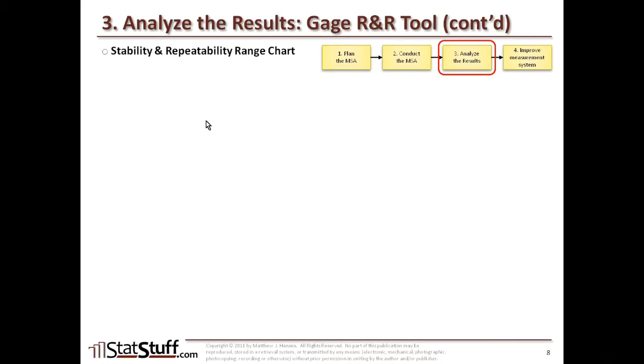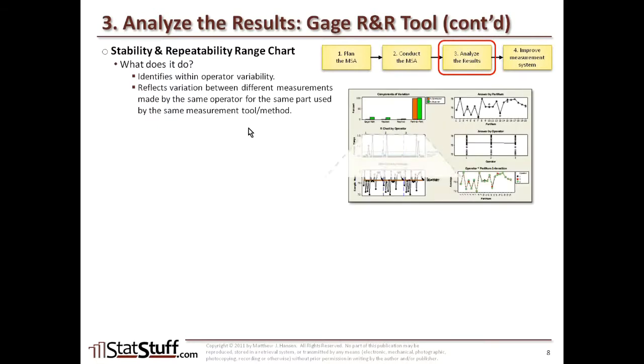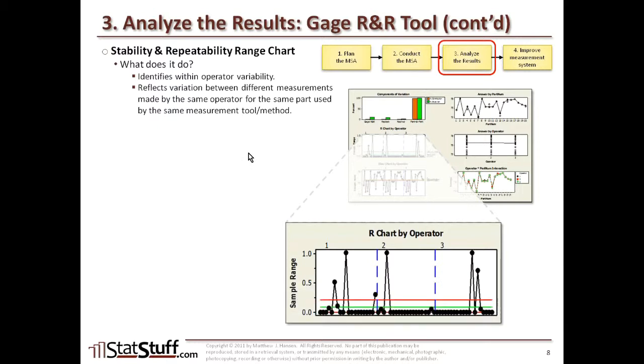Let's start with the stability and repeatability range chart. This chart identifies within-operator variability — it reflects the variation seen between different measurements made by the same operator for the same part using the same measurement tool or method.